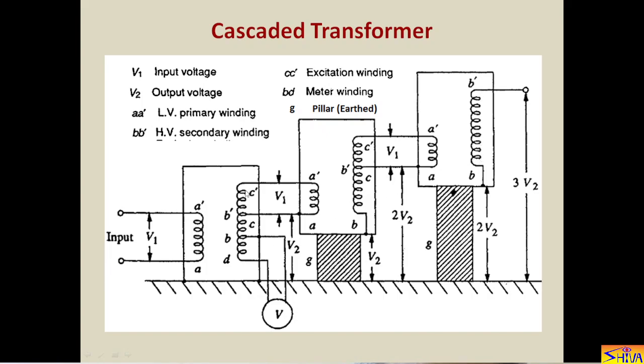CC' is the excitation winding connected to the primary winding of the second unit. The voltage induced in this excitation winding is the same as V1, so V1 is given to the low voltage winding of the second unit. Similarly, in the second unit CC' is the excitation winding connected to the primary winding AA' of the third unit. This voltage is also V1, so the voltage induced in the secondary winding for all units is V2.